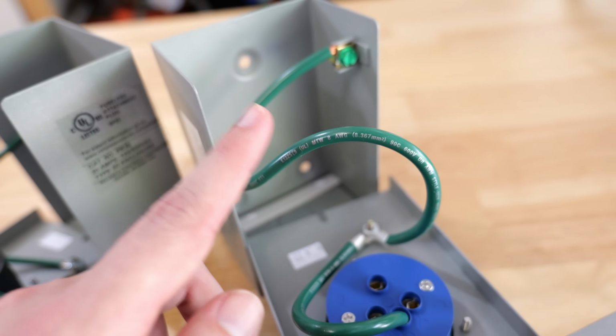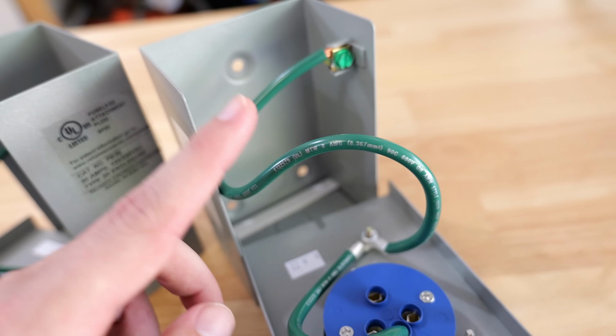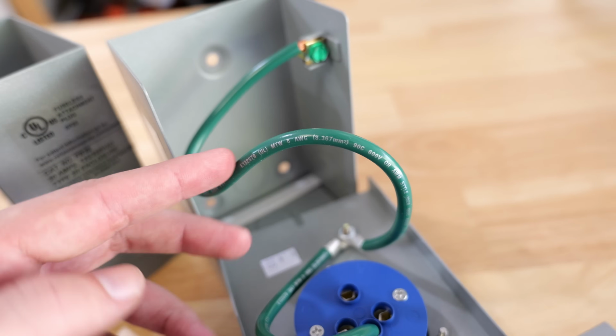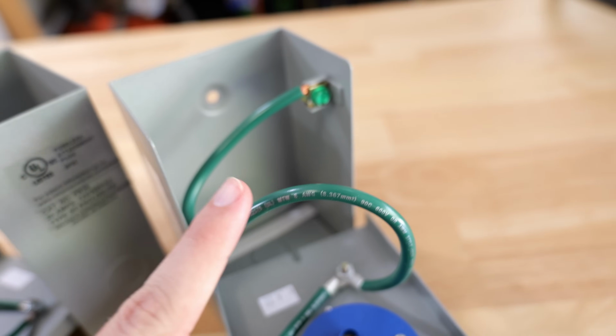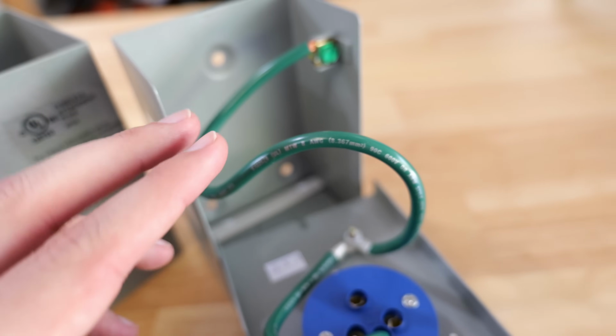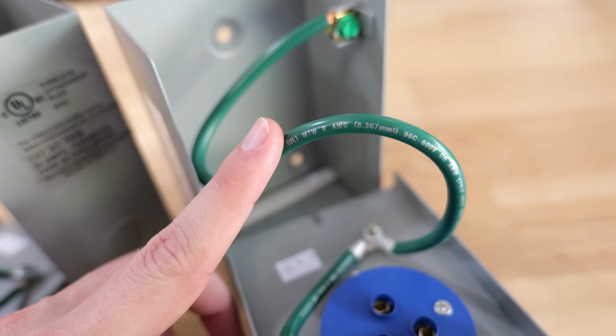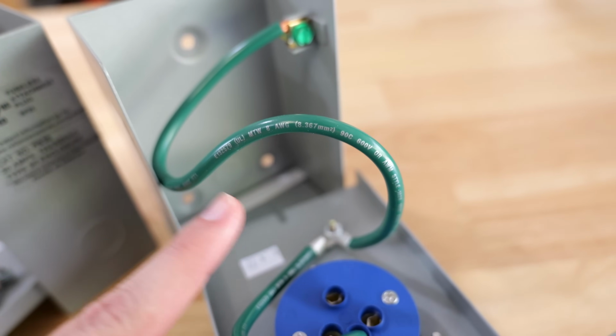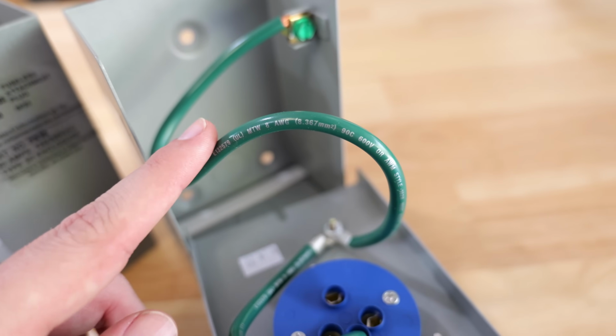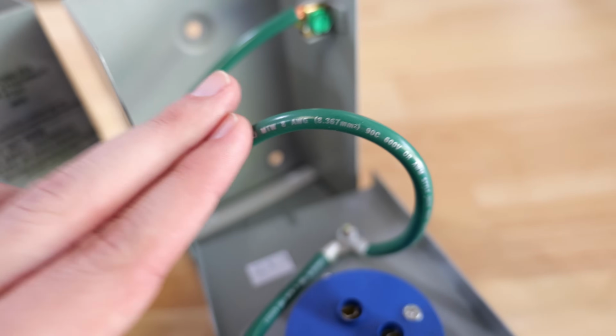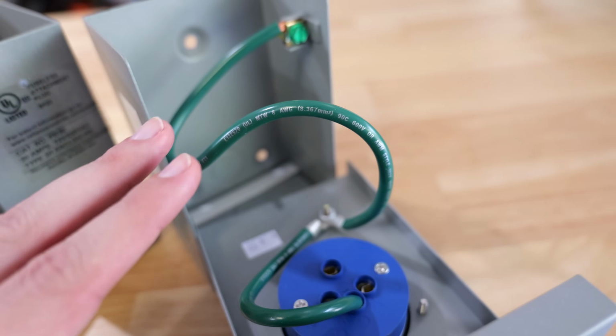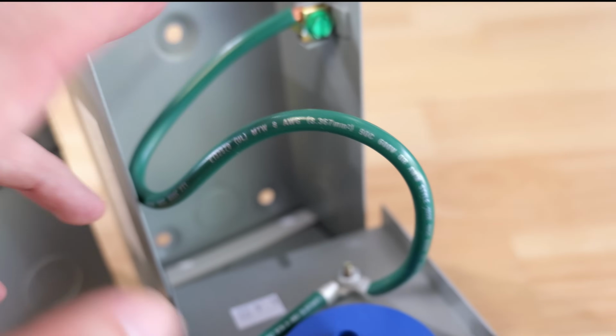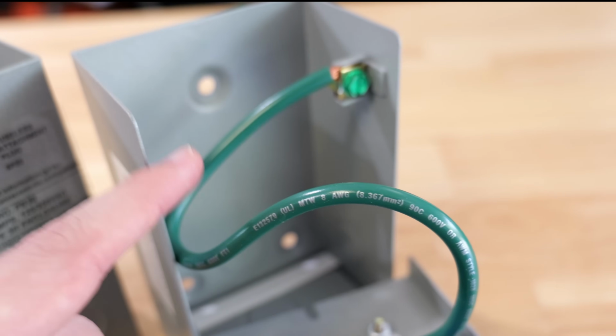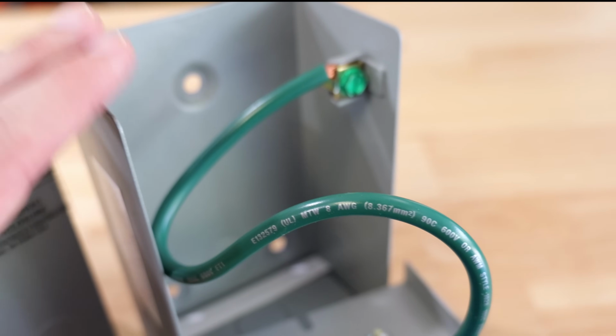It's 8 gauge wire. Now for me personally, when I'm installing a 50 amp power inlet box, I like to run 6 gauge wire. Some will argue that 8 gauge is enough, but it's going to completely depend on the kind of wire that you install. But I prefer to install 6 gauge wire because I know that I'm covered and have big enough wire. But as far as this grounding wire goes, for it just bonding the box and it being as short as it is, the number 8 in this box is completely fine for this 50 amp application. But all the rest of my wires, if I was installing this today, I would be using 6 gauge wire to connect this then to my panel.